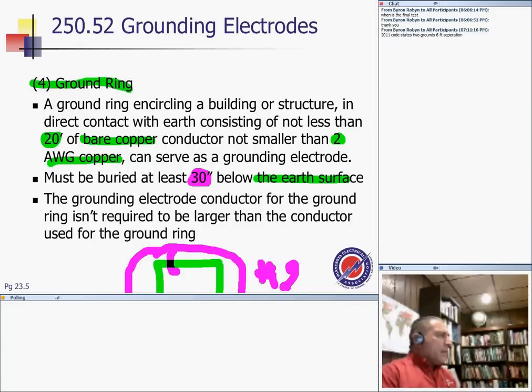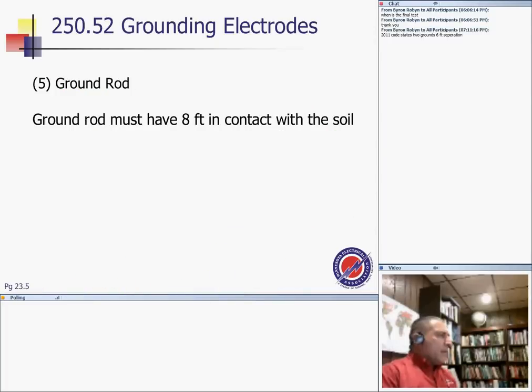The grounding electrode conductor does not need to be larger than the grounding ring. What I'm trying to say here, guys, is they're saying, oh, by the way, if this is number 2, then this conductor doesn't have to be more than number 2, regardless of what 250.66 states. And as for the ring, it's another option for you to ground the system. Remember, we're grounding systems here, guys. To ground the system, the ring. Here are the ground rods. We're familiar with the ground rods. Ground rods must have 8 feet in contact with soil, and there are some restrictions in the size and so forth.